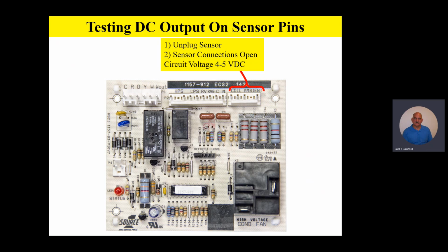Now, team, this is very, very important. If I have 24 volts on the board between C and R, our previous check, and I do not have 4 to 5 volt DC on the coil pins and the ambient pins, then the board is bad. You don't have to go any further. You know that the board is not supporting the sensors because it doesn't have the DC output of 4 to 5 volt DC on the pins.